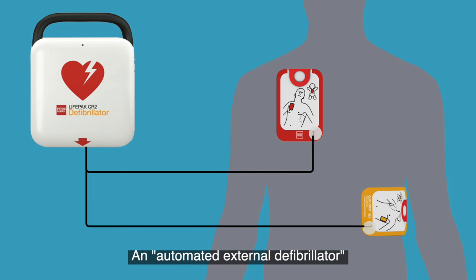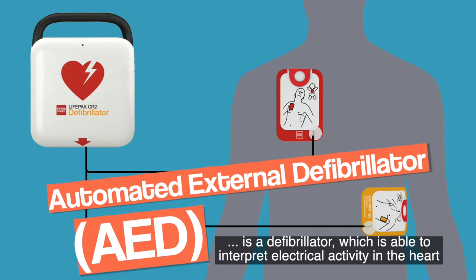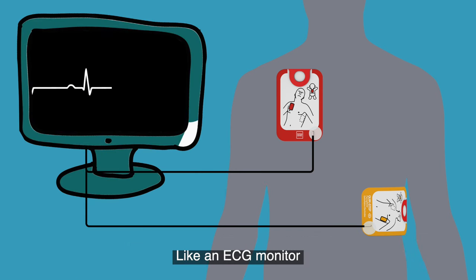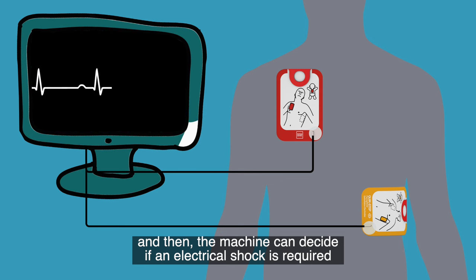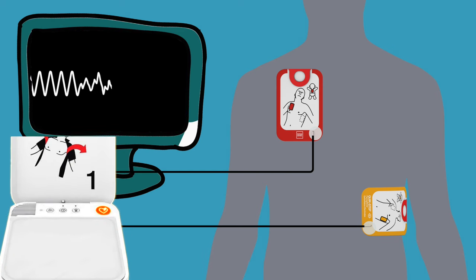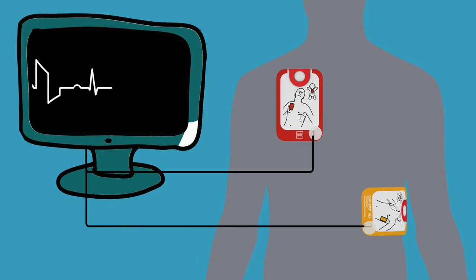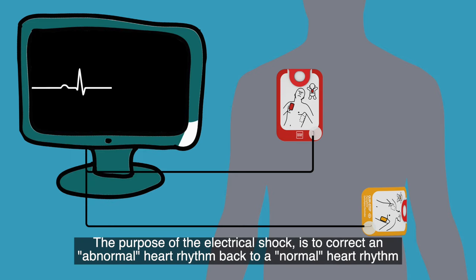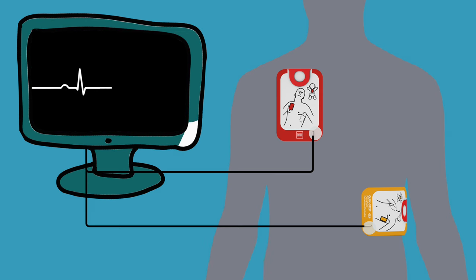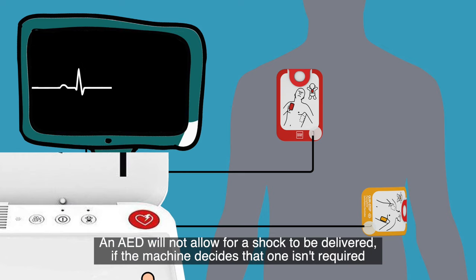An automated external defibrillator, or AED, is a defibrillator which is able to interpret electrical activity in the heart like an ECG monitor, and then the machine can decide if an electrical shock is required. The purpose of the electrical shock is to correct an abnormal heart rhythm back to a normal heart rhythm. An AED will not allow for a shock to be delivered if the machine decides that one isn't required.